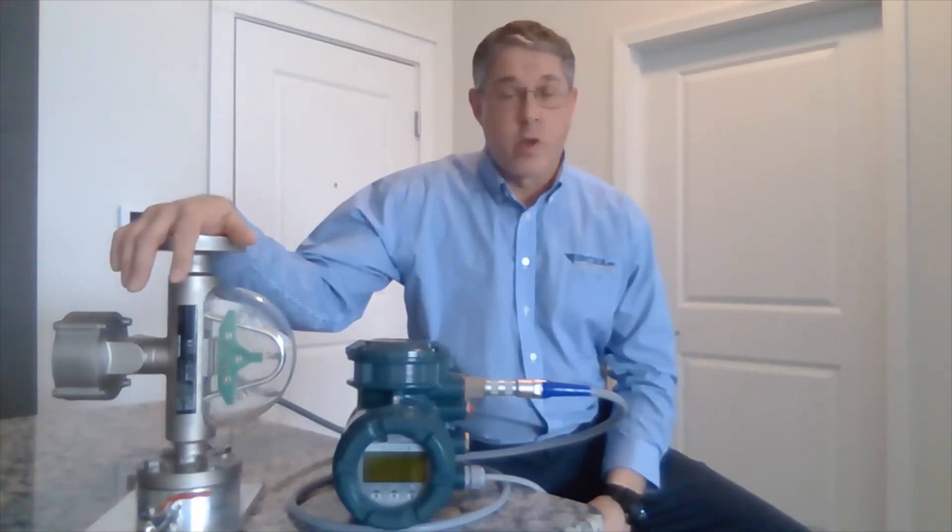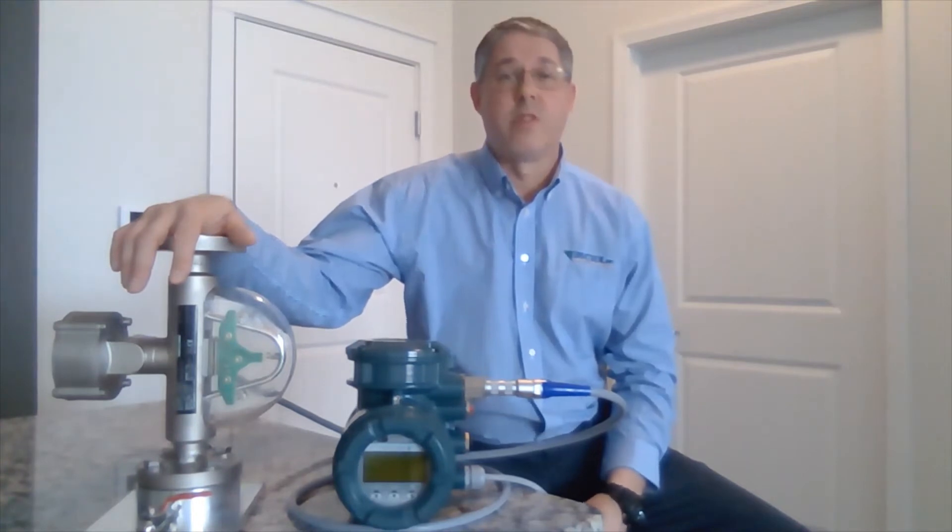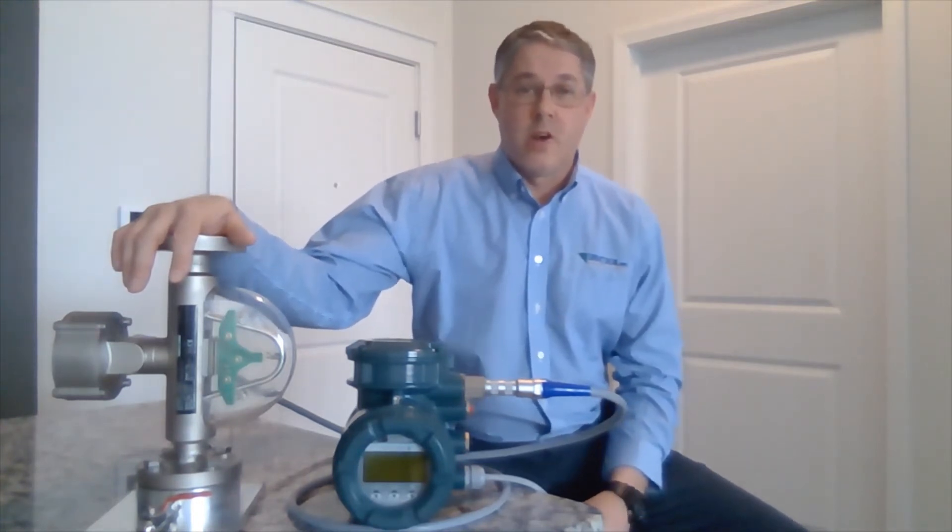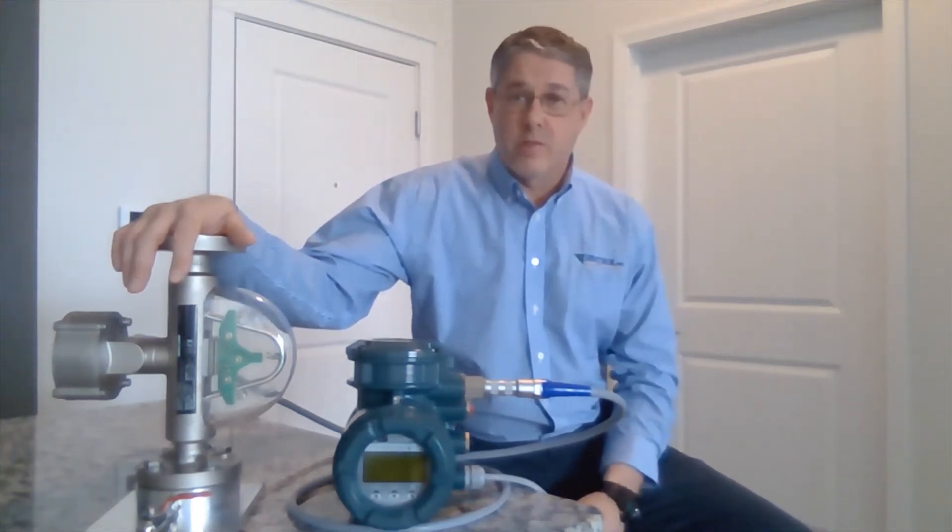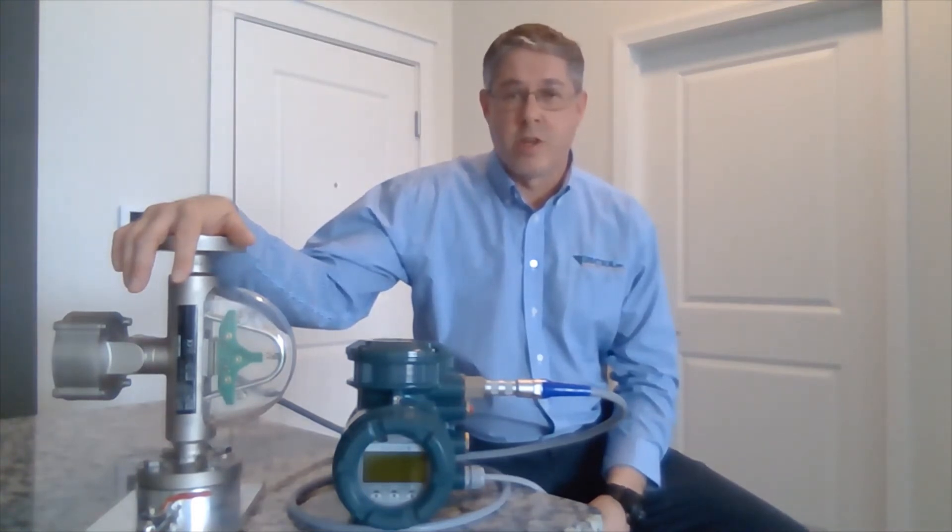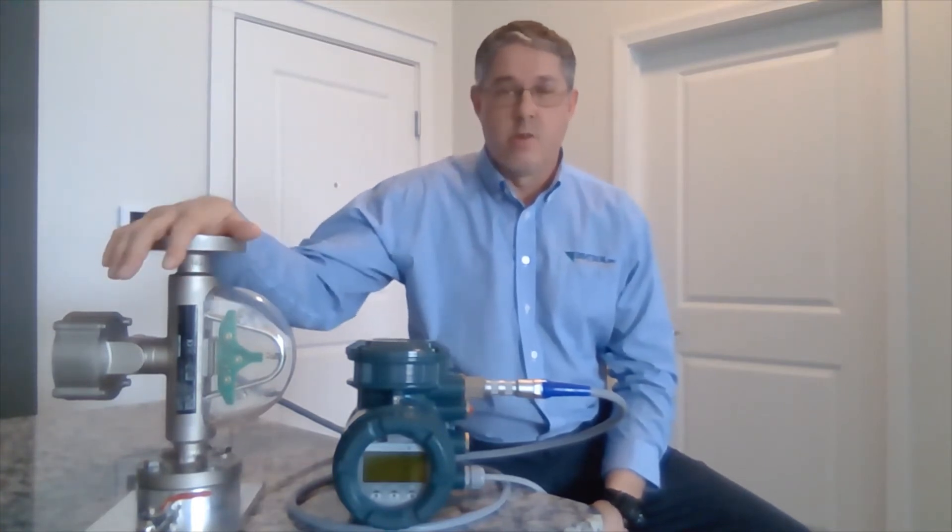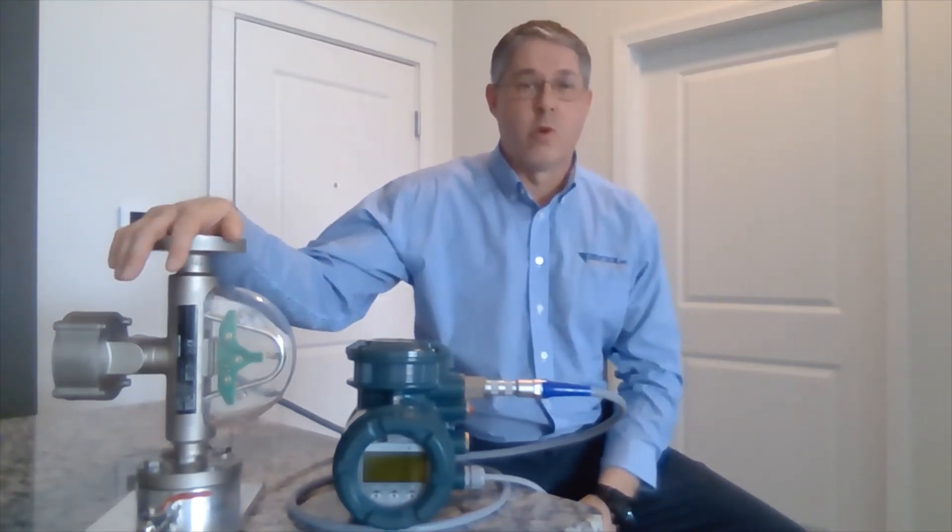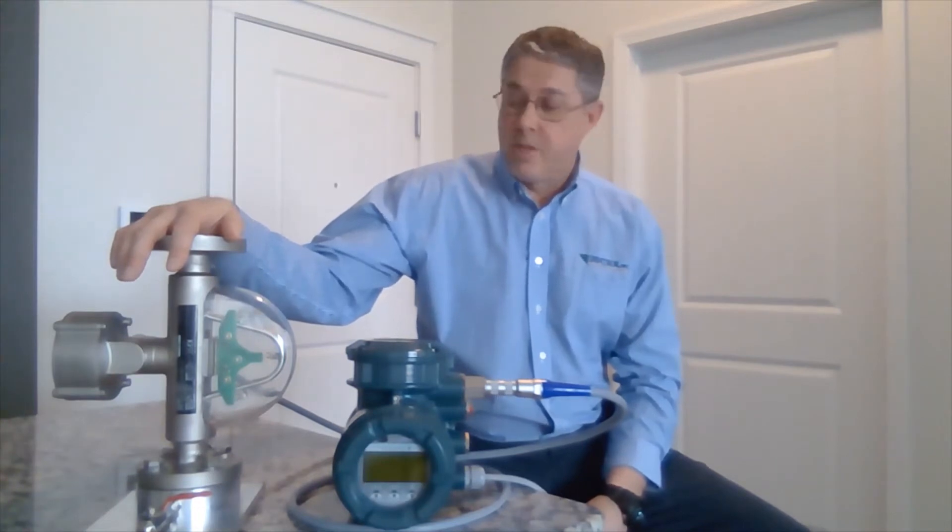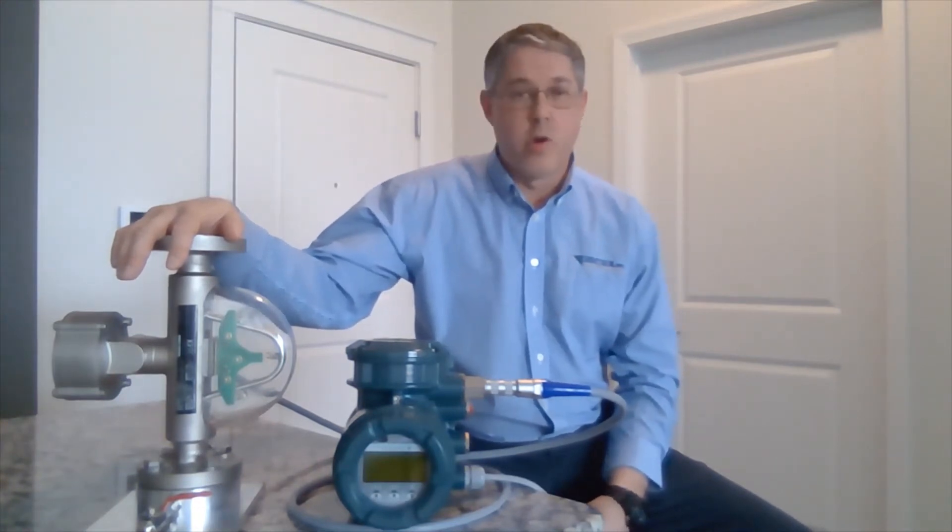There's no need for a flow conditioner before or after the metering point. There are no straight run requirements like there are in other technologies of flow measurement. You don't need 10 and 5, you don't need 20 and 10 - you need zero straight run requirements for a Coriolis meter. There's no moving parts in a Coriolis meter, which means less wear and tear, little to no maintenance on the meter.